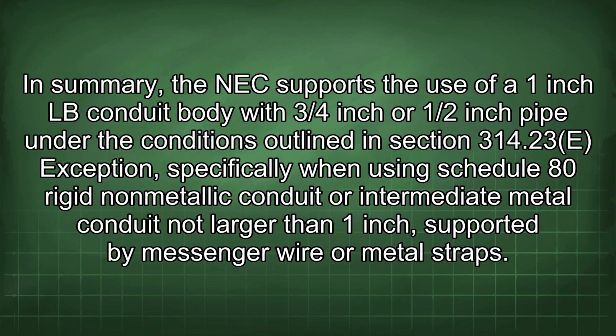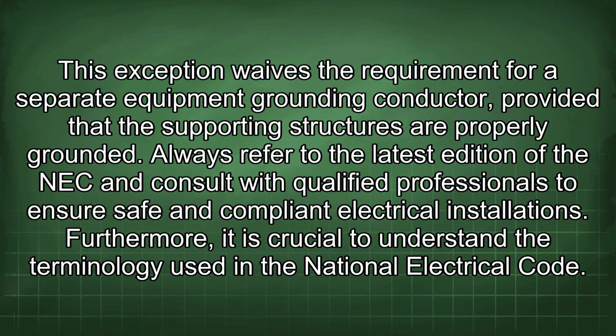In summary, the NEC supports the use of a 1-inch LB conduit body with 3/4-inch or 1/2-inch pipe under the conditions outlined in the Section 314.23(E) exception, specifically when using Schedule 80 rigid non-metallic conduit or intermediate metal conduit not larger than 1 inch, supported by messenger wire or metal straps. This exception waives the requirement for a separate equipment grounding conductor, provided that the supporting structures are properly grounded. Always refer to the latest edition of the NEC and consult with qualified professionals to ensure safe and compliant electrical installations.